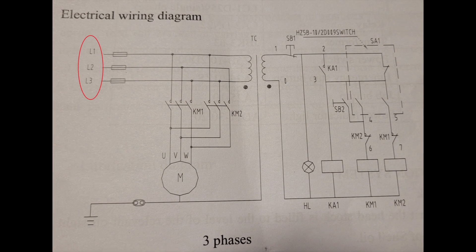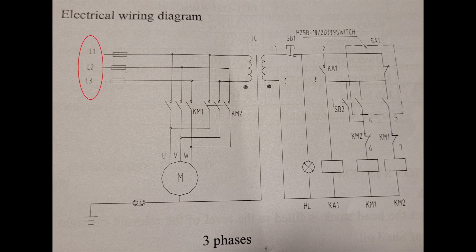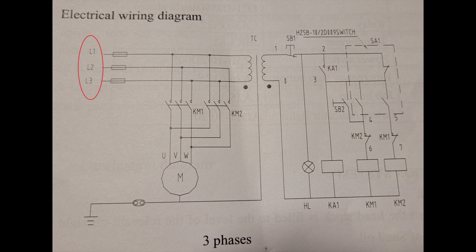This schematic shows how the lathe was originally delivered with three input legs: L1, L2, and L3. I'm going to completely remove the components, contactors, and wiring, and convert it to L1, L2 single-phase 240 volt for residential use.